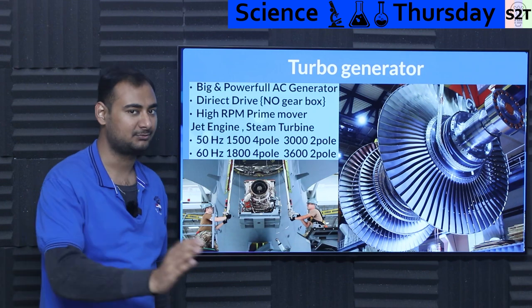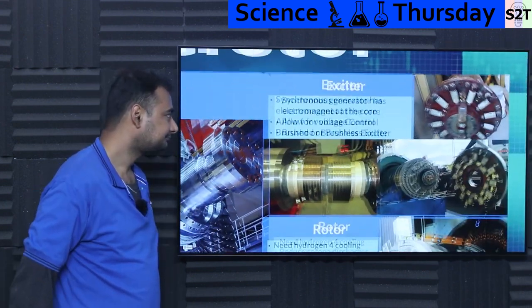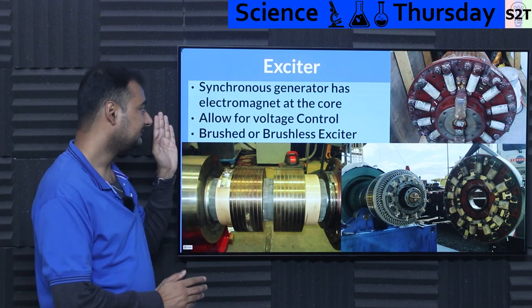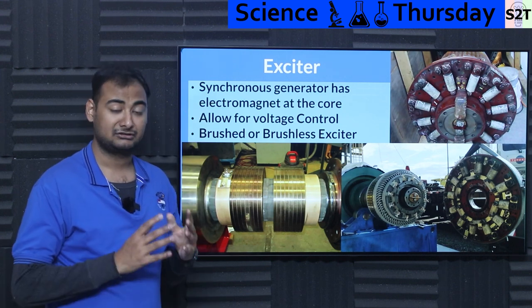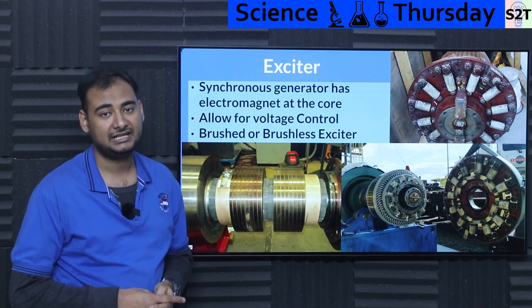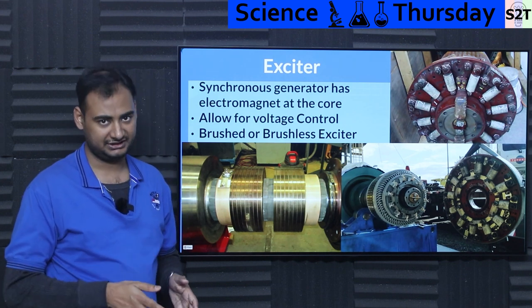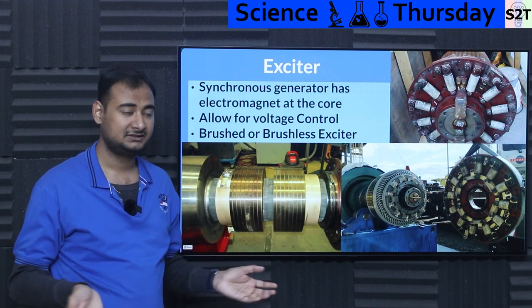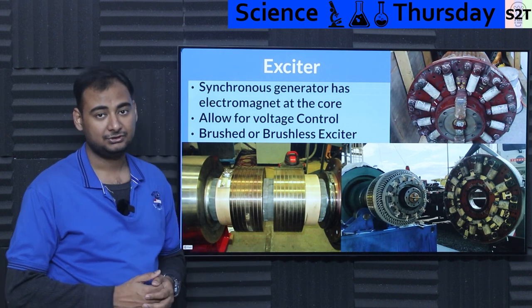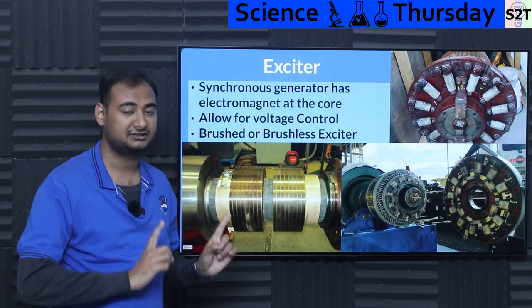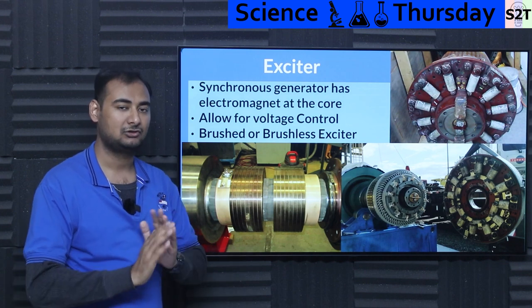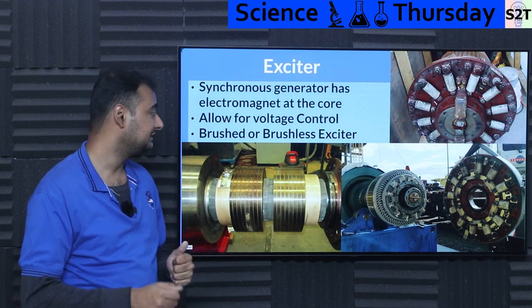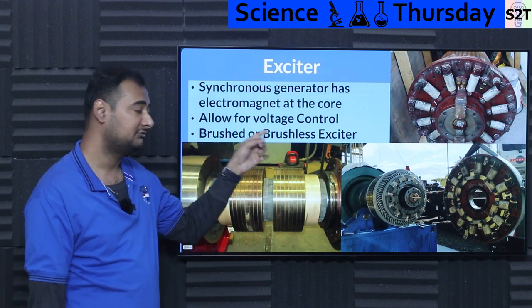Because these are synchronous generators, they require an electromagnet at the core. Can we replace that with a permanent magnet? Yes, but if you do that, you lose voltage control — the voltage is no longer adjustable. So you have to use an electromagnet. Being synchronous means RPM directly translates to frequency, with no sloppiness like in induction machines. Synchronous gives you frequency lock; the electromagnet gives you voltage control.